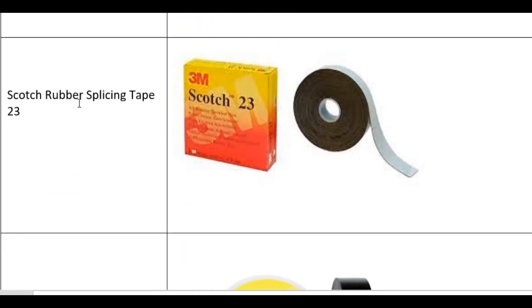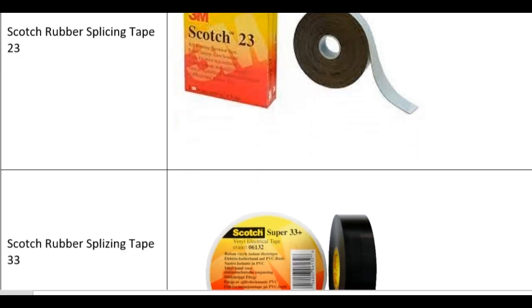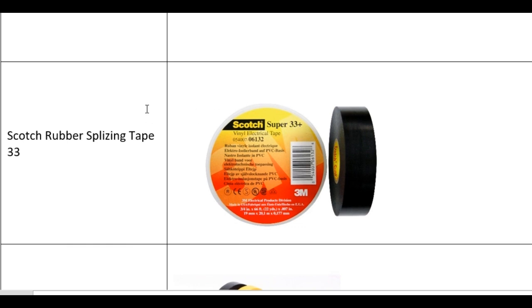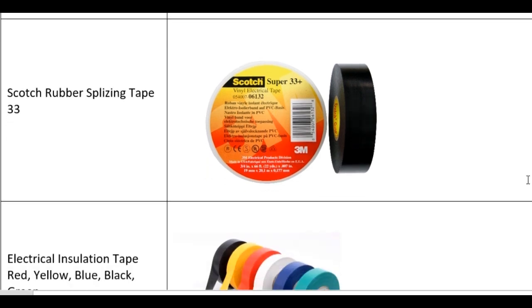Next one is Scotch rubber splicing tape 23, mostly used in waterproof applications and all outdoor purposes. Scotch tape 23 can be used as an insulation for low voltage applications as well as an insulation for splices up to 69,000 volts. Next is Scotch rubber splicing tape 33, Scotch Super 33. Scotch 33 is designed for above and below grade, indoor and outdoor, low and high voltage applications and for harnessing cables.